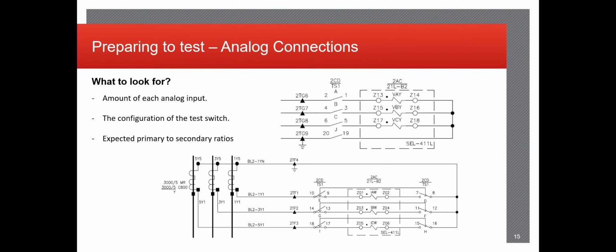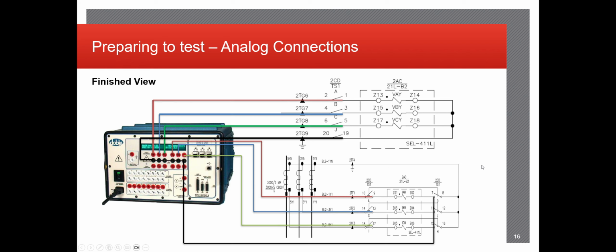So when you supply 5 amps into this example here, the relay should see 3000 based on the CT ratio that is shown in the circuit. And if it's not, then that's something that you mark, fix, and report back. This is what it would look like if you plugged it into the test set fully. You see all your voltages here on the left going in, your A, B, and C, which was designated based on the prints, as well as your currents over here, A, B, and C, per the prints.